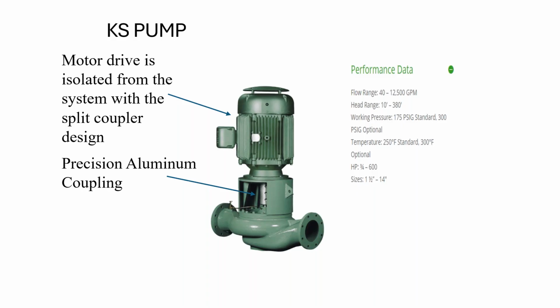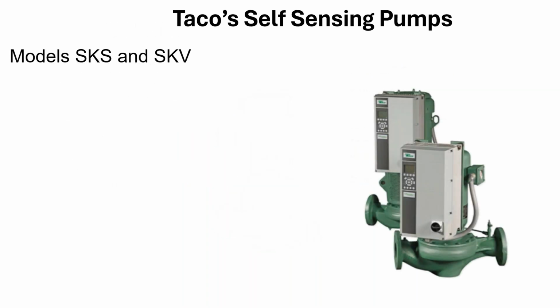Notice in the performance data, the range goes over 12,000 GPM. I think we even go higher than that now, but they could get pretty big. And we were touring the factory last week with some guests, and we had some big boys out there in the factory that were being final assembled. Actually, a couple were assembled and they were being crated up, and they had 200 horse motors on them, and they get pretty big.